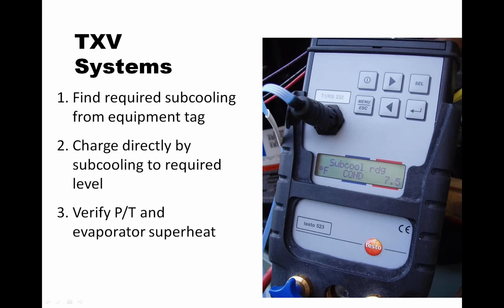TXV systems find the required subcooling from the equipment tag and charge directly to the subcooling requirement level. In this case, this unit I was working on a couple years ago, this is an older Testo 523, required 8 degrees of subcooling, and we're right at 7.5 degrees, right? Now after we're done, we need to always verify both sides of the system.